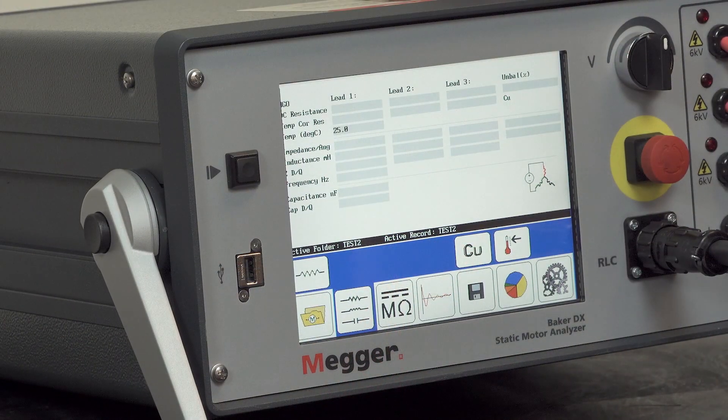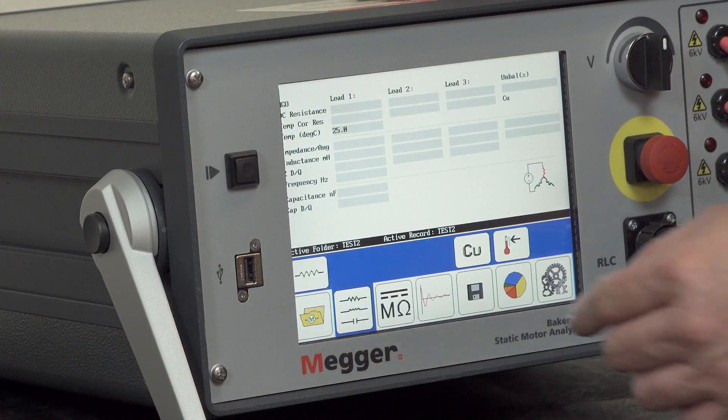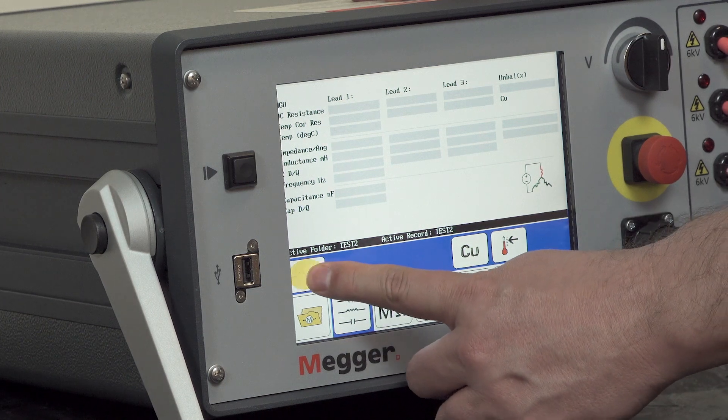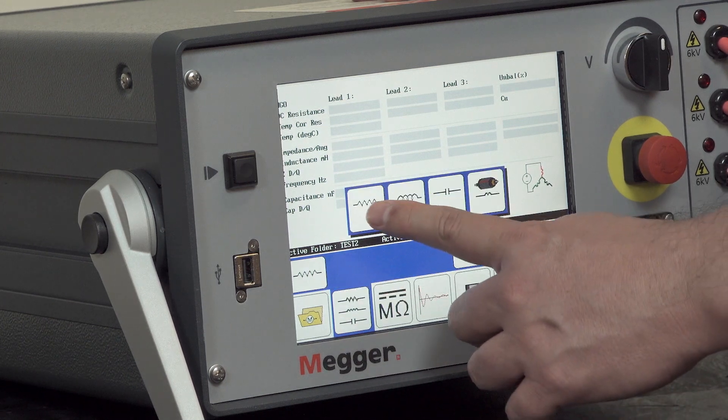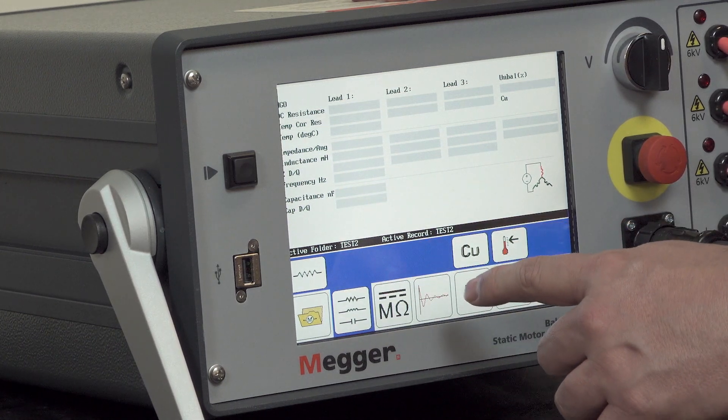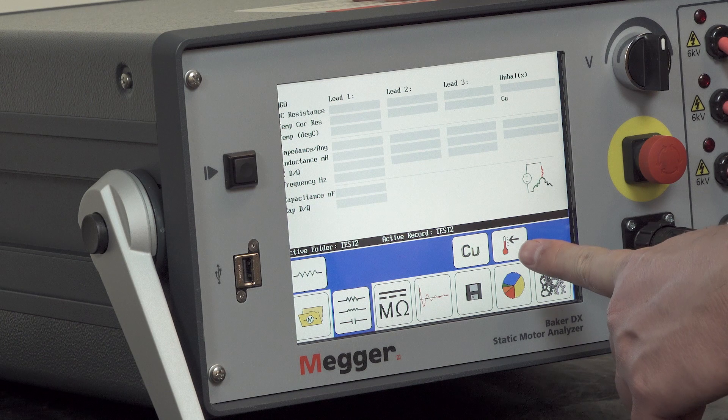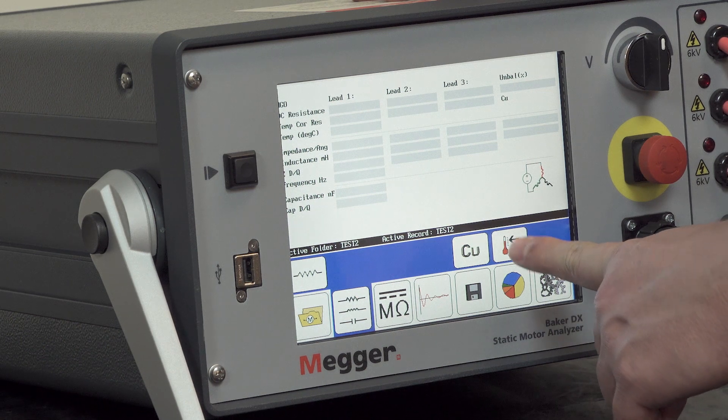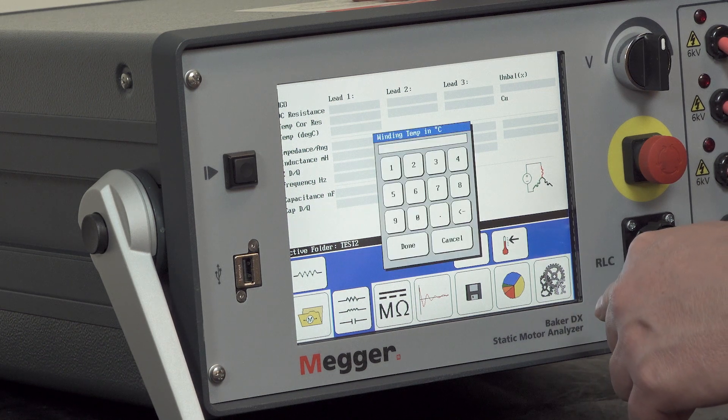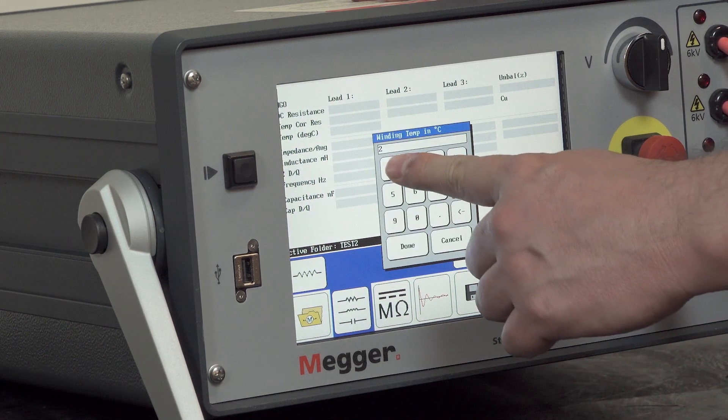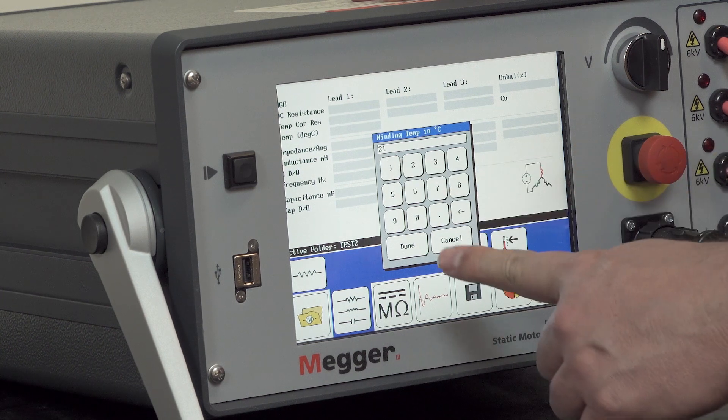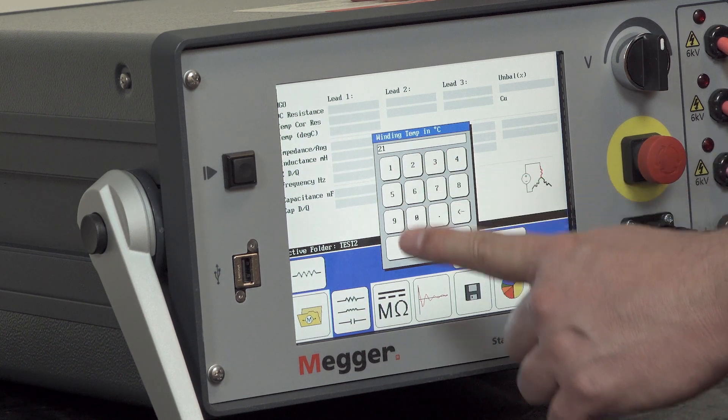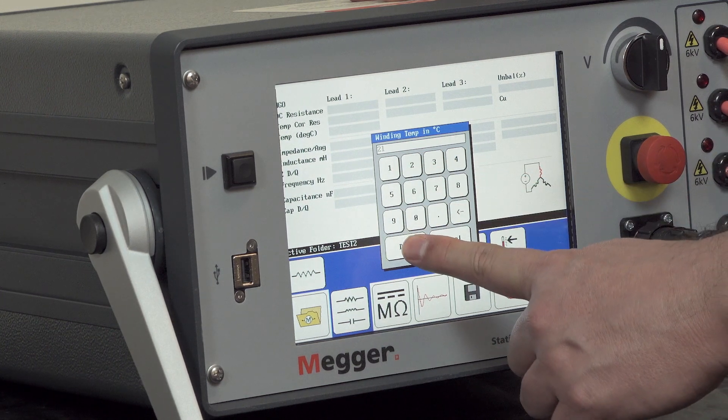Okay, so to perform the resistance testing we'll make sure we select the resistance mode first. If we want to do temperature compensation we should select the temperature icon, enter the temperature of the winding under test, and then select done.